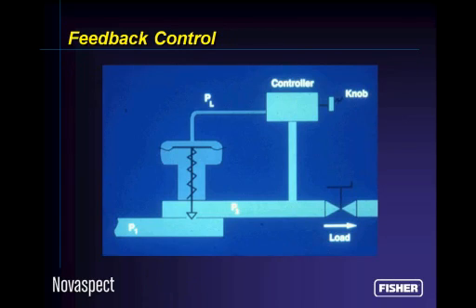Almost every control valve is part of a feedback control system in which we measure a variable, like, for example, this could be the steam pressure, P2, downstream of a control valve. Our objective is to control that pressure. We could have something as simple as a pneumatically operated pressure controller. For example, you might be familiar with the Wizard pressure controller. There's a knob in there which you use to set the set point for the pressure you'd like to see in pipe P2. It sends a loading pressure to the actuator, which positions the valve plug against the seat ring to a certain position so that just enough steam gets through this P1 to P2 to maintain P2 at the steam pressure where you want it, regardless of what the load might be. If you go down there and you grab that valve called the load valve, you change its position, this whole system, this feedback control system, will respond to restore the pressure to the set point.